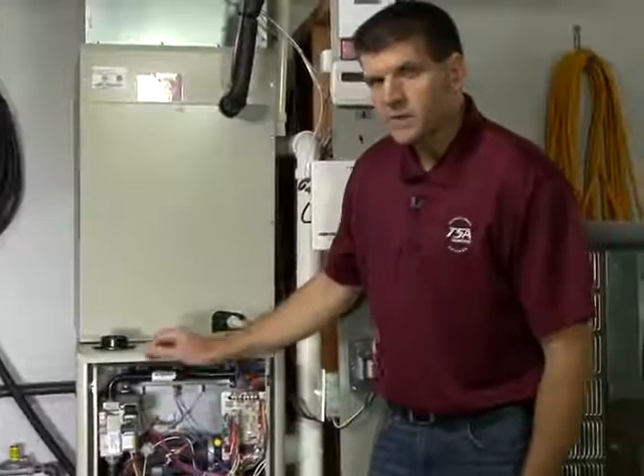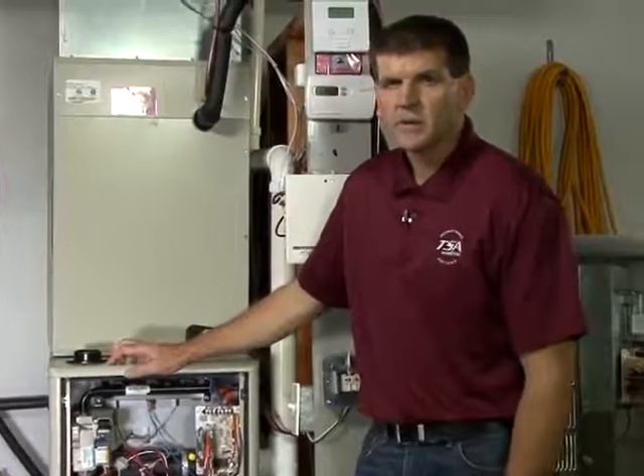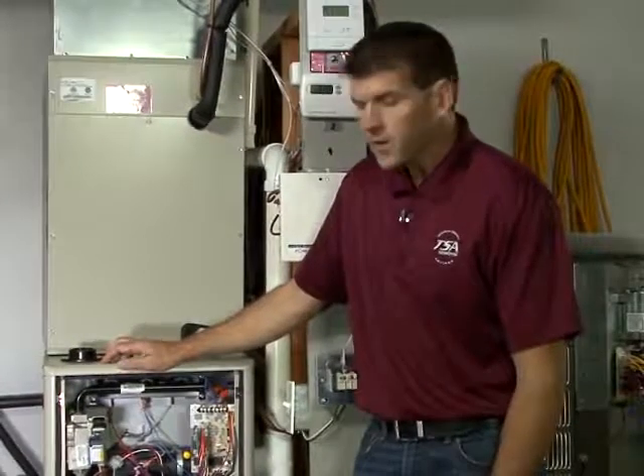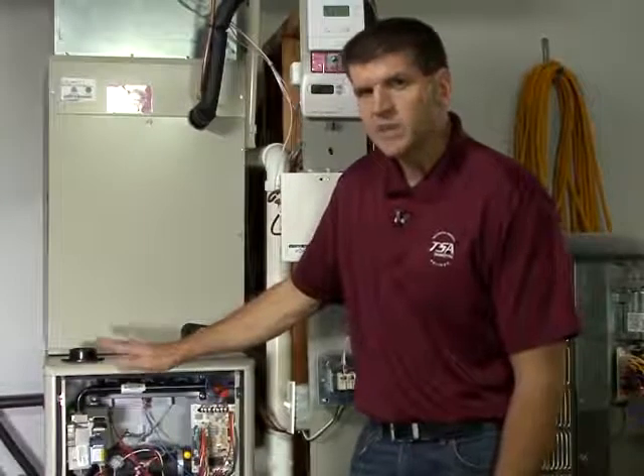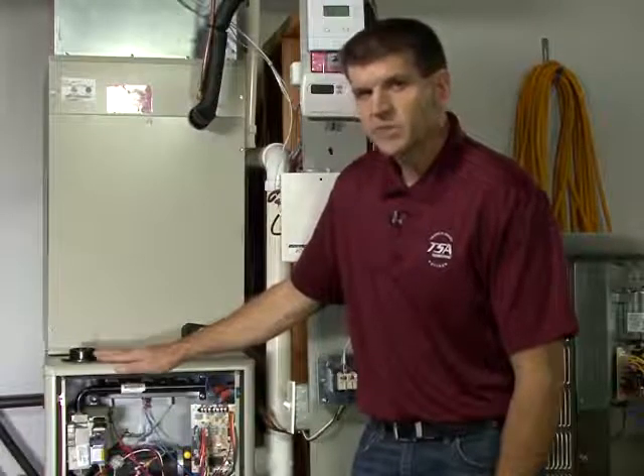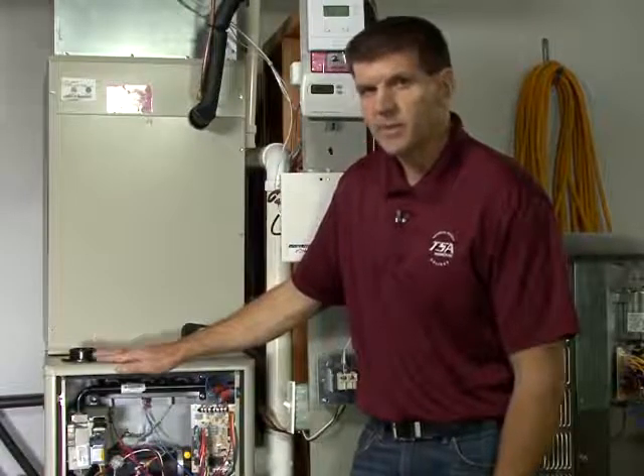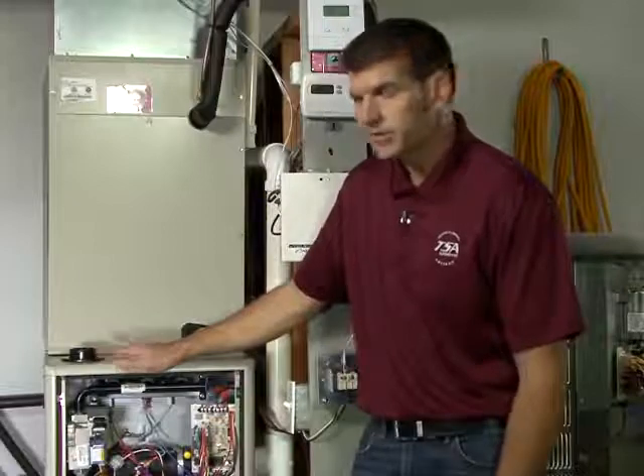The most common cause for limit switches to open is low airflow. Low airflow across the furnace cabinet or across the heat exchanger will cause the furnace to run at abnormally high temperatures. Remember, low airflow equals high temperature rise. If we are getting a high temperature rise, we're most likely operating at temperatures that are at or above the set temperature on the switch, causing the switch to open.